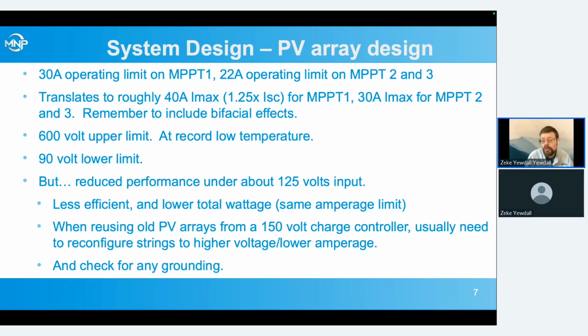And also older modules had a higher temperature coefficient, so they'd actually climb more in cold weather than a lot of the newer modules, which are a little more temperature stable. But still, where I'm working, usually I'm around minus 30 centigrade for our winter low temperature. And that's a 16 to 20% increase in voltage. So keep that in mind when calculating lengths of strings for staying below that 600 volt upper limit.